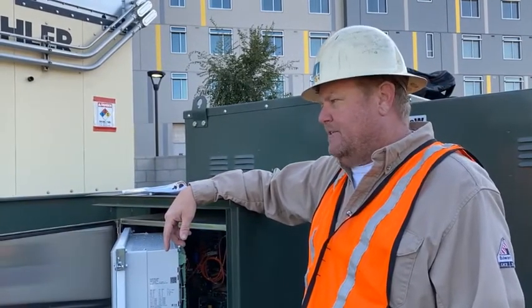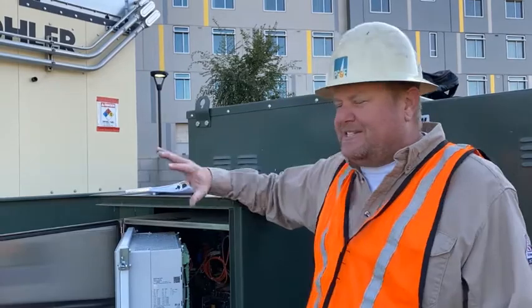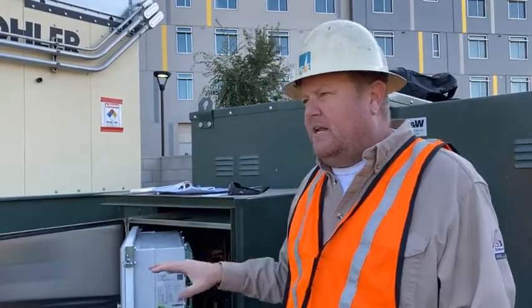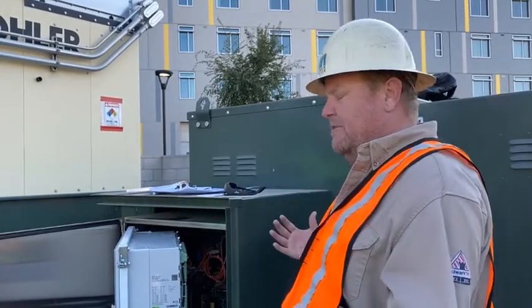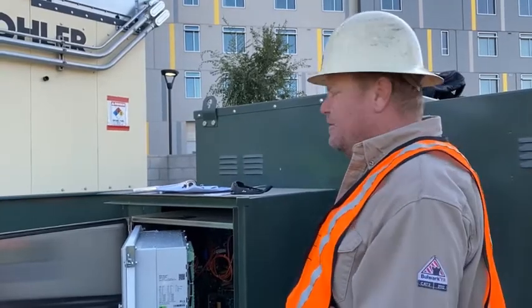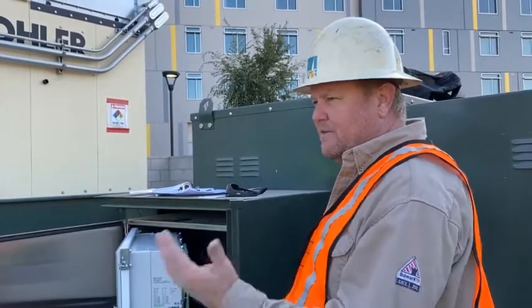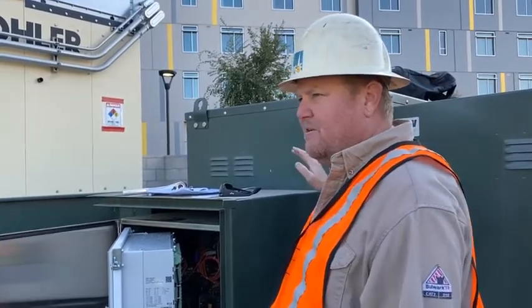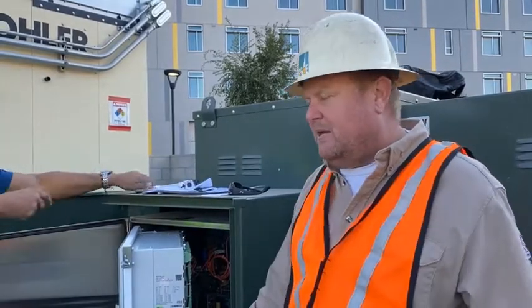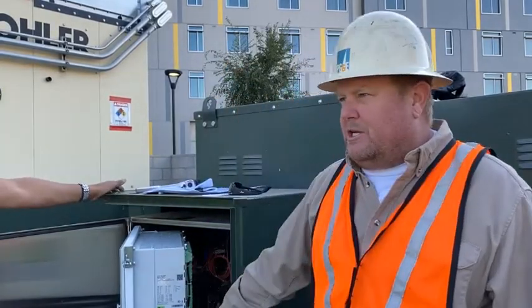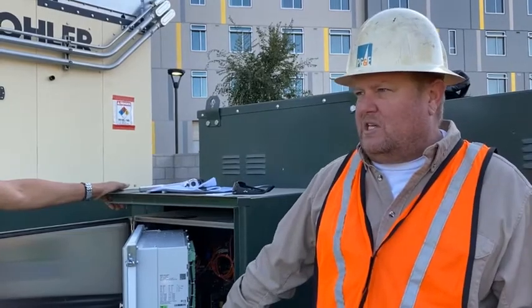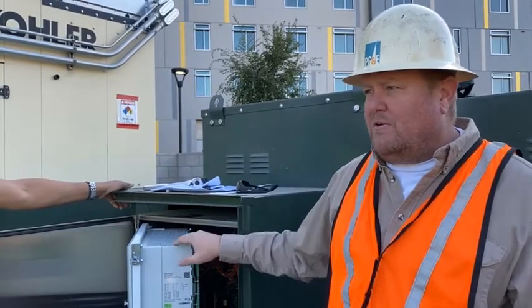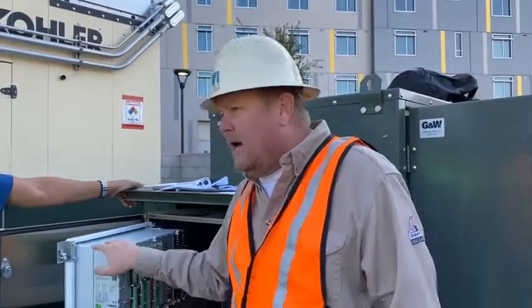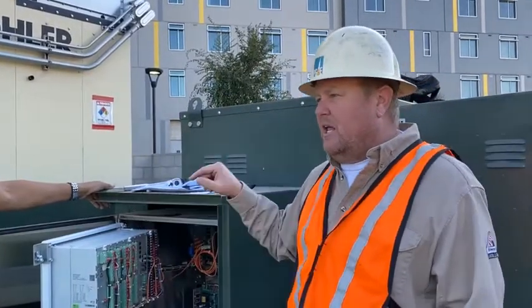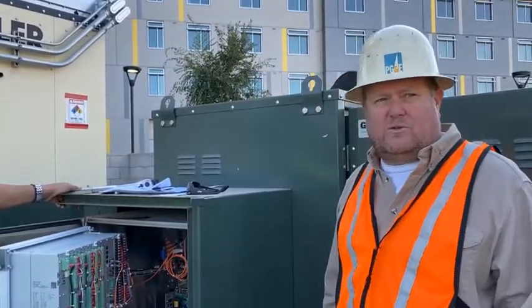If you ever run into that problem where the power goes out and you only have one feeder and it's not set up for auto transfer, and it sits for 8 hours de-energized, the battery runs down, you can either bring 24 volt DC and jump it in there, or bring in 120 volt AC and jump it in there, bring it back up, and then you can electrically operate the sources.